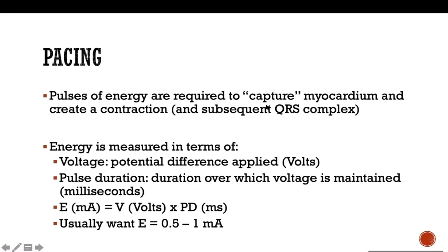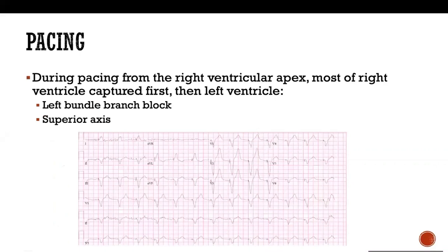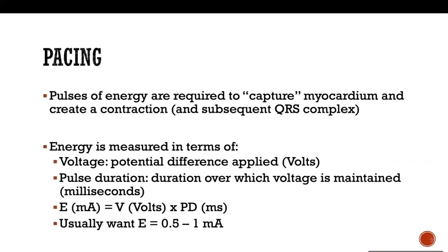So the lower the amount of energy required to capture the myocardium, the lower the threshold. So the threshold is the minimum amount of energy required. So for example, if you're delivering an energy of 1 volt and you're not creating a myocardial contraction, you increase the energy to 1.5 and you're still not capturing the myocardium, then you increase the energy to 2, and at 2 you're capturing the myocardium. So the threshold is the minimum amount of energy required, which in this example is actually 2.